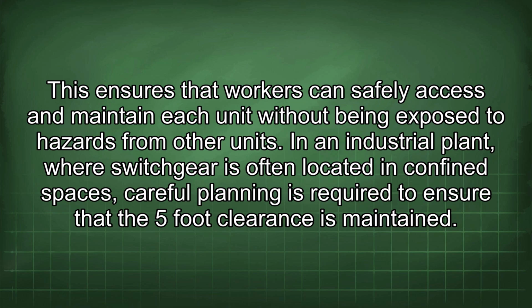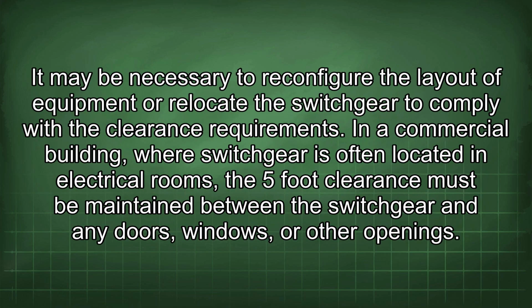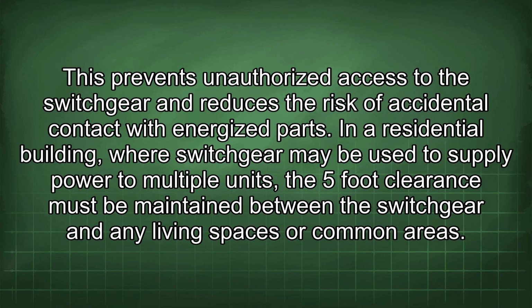In an industrial plant, where switchgear is often located in confined spaces, careful planning is required to ensure that the 5-foot clearance is maintained. It may be necessary to reconfigure the layout of equipment or relocate the switchgear to comply with the clearance requirements. In a commercial building, where switchgear is often located in electrical rooms, the 5-foot clearance must be maintained between the switchgear and any doors, windows, or other openings. This prevents unauthorized access to the switchgear and reduces the risk of accidental contact with energized parts.